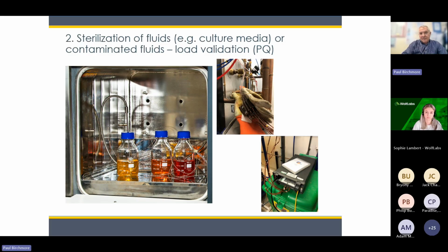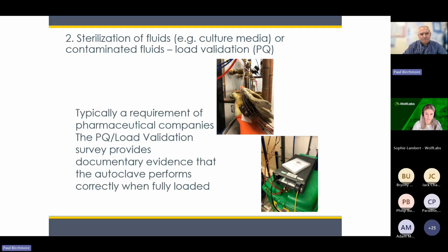And that's your evidence. And if during that process the engineer discovers that there isn't a successful result, then he will change those settings. So instead of the dreaded 121 for 15, it might change to 123 for 20, or any other permutation of subtle differences in temperature and time, because that would be the specific requirements of the materials involved. It might take longer to heat up. It might take longer for the stabilization of the material to reach that temperature. That's when the expertise of the load validation process kicks in, and we can change the settings subtly to prove that the whole process has been successful.